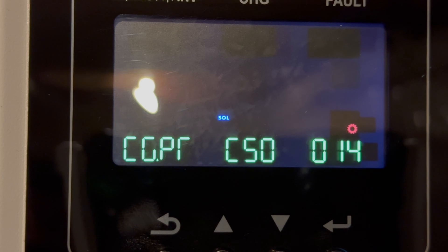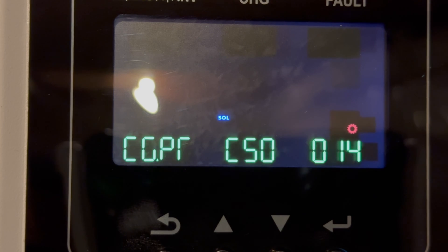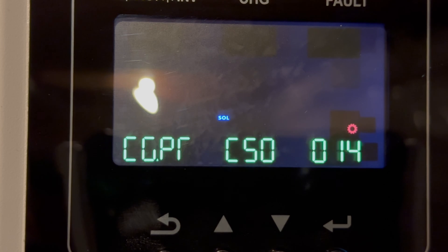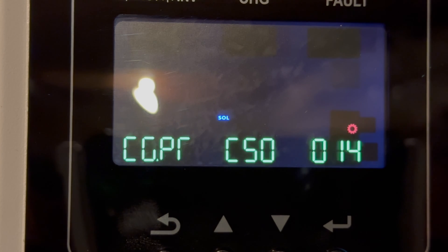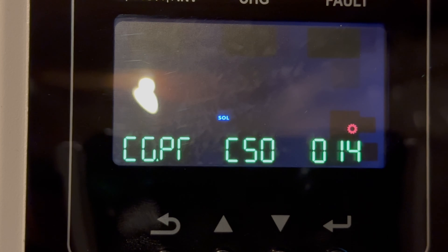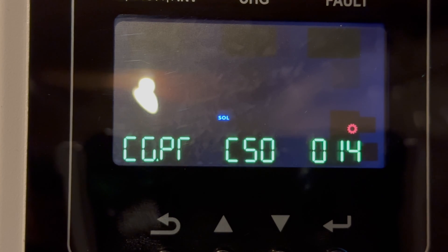Setting 14 determines which source charges the battery — solar or grid. In CSO mode, solar is the priority, then grid. If the sun were to go down, the grid can charge it, but we restrict the time in which the grid can charge the battery to late at night, so this is not an issue during the day.